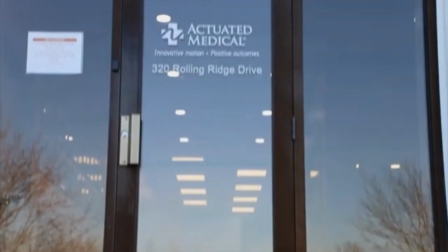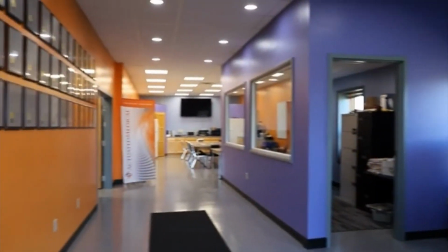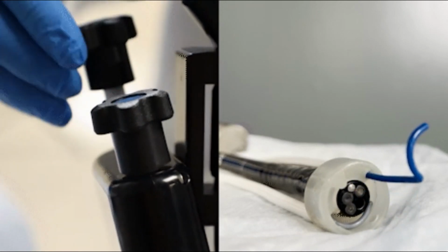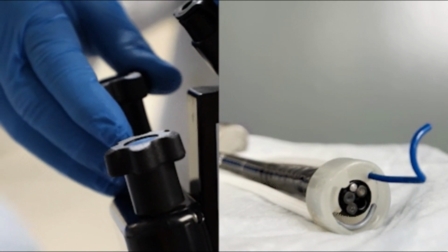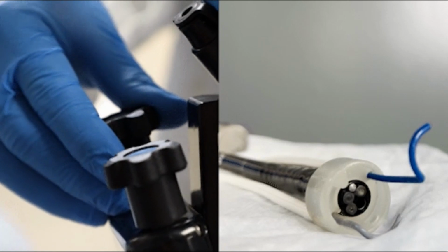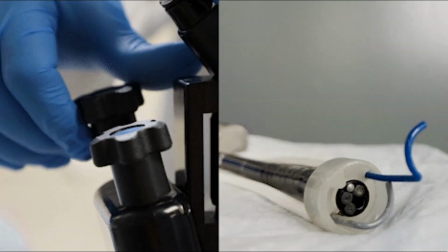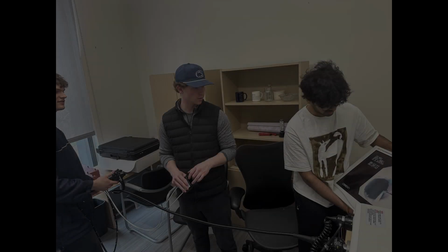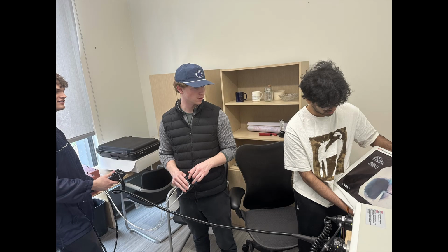Our group was initially retained by Actuated Medical to evaluate the effectiveness of their FDA-approved device, the GripTract. This device is currently approved for tissue manipulation during gastrointestinal procedures. We wanted to explore a new question. Could the GripTract also be used to retrieve foreign bodies from the GI tract? To answer this, we needed a realistic testing setup. Since no suitable products currently exist in the market, we decided to develop our own synthetic GI tract simulator.